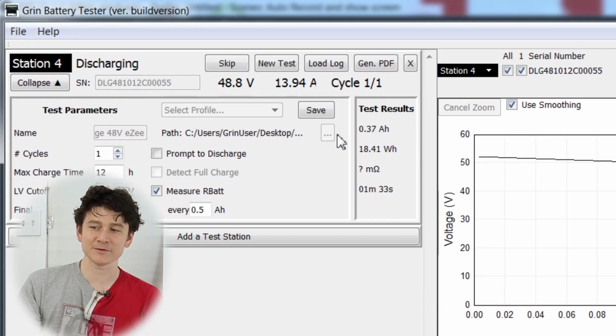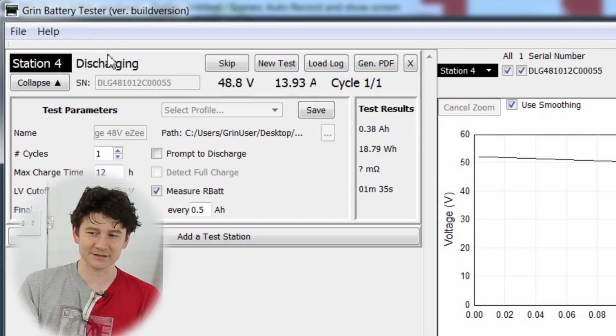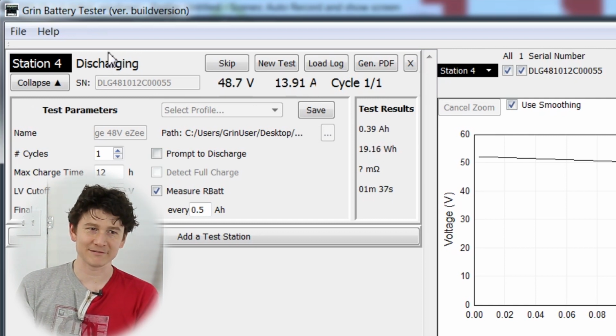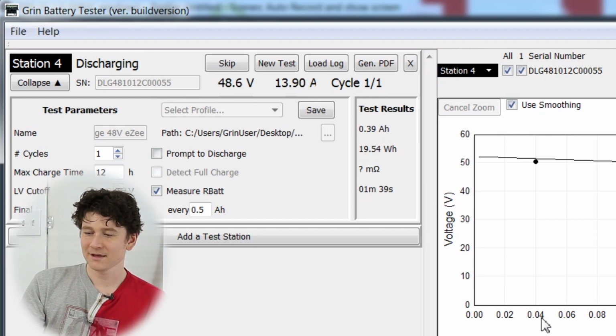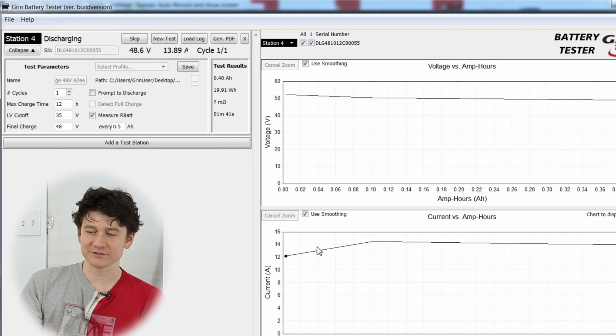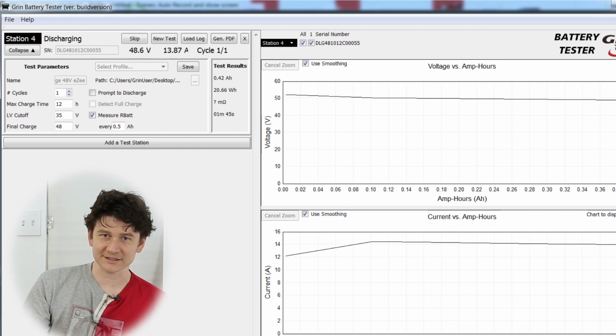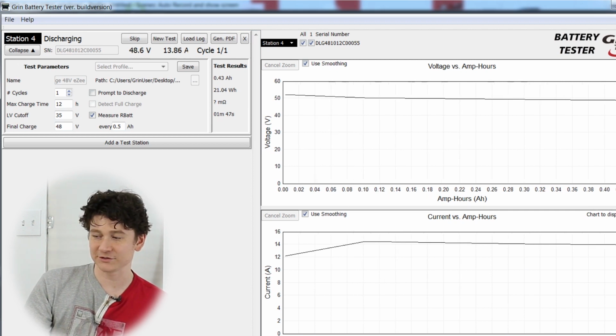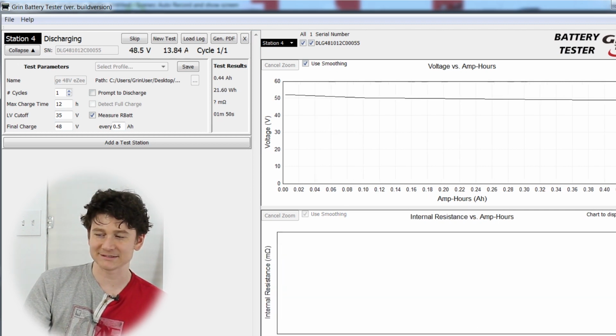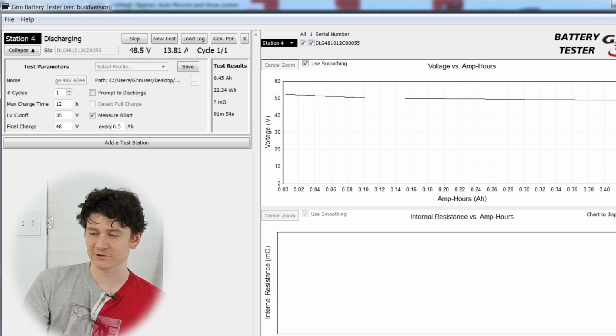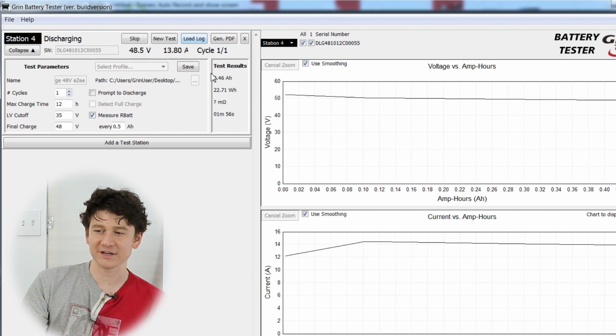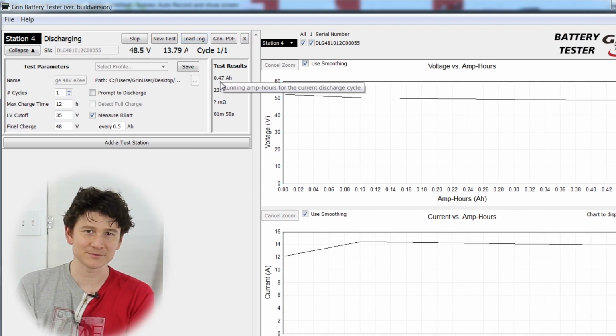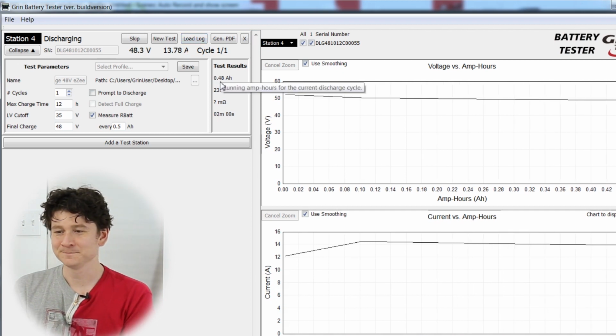Right now we're at 0.36, 0.37 amp hours. We're just going to wait a little longer, and then you'll get to witness one of these battery internal resistance measurements. The second graph I showed is displaying the discharging current, but we can change it to show an actual readout of the battery resistance test. Up to this point there's been no resistance test, so there's no graph yet, but that will change once we get to 0.5 amp hours, which is coming up imminently.